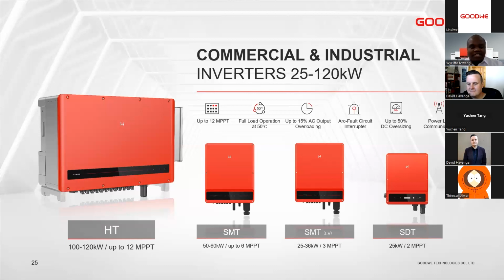We also have the SMT series 50 and 60 kilowatts. In this case, the 50 kilowatt comes with up to 5 MPPTs, and the 60 kilowatt comes with up to 6 MPPTs. We have the large commercial and industrial inverters in the sizes of 100, 110, and 120. The 110 comes with 10 MPPTs, while the 120 comes with up to 12 MPPTs. So really, this gives you multiple trackers to reduce the losses when you're doing your design.